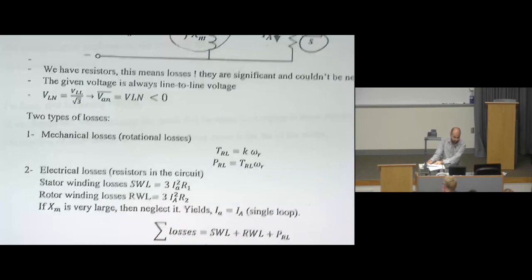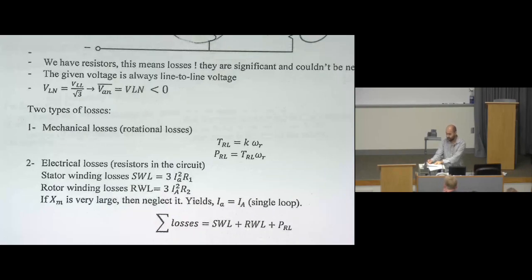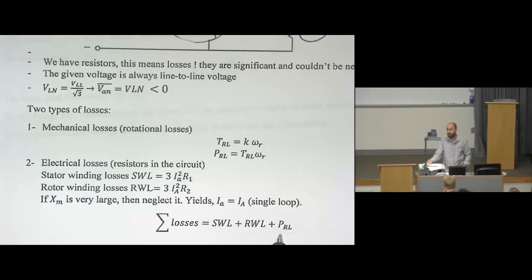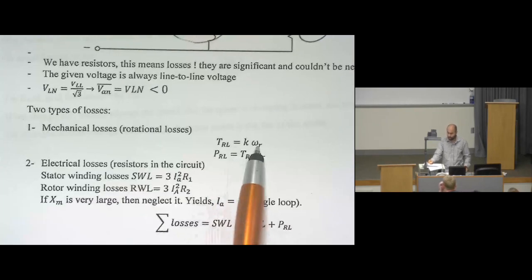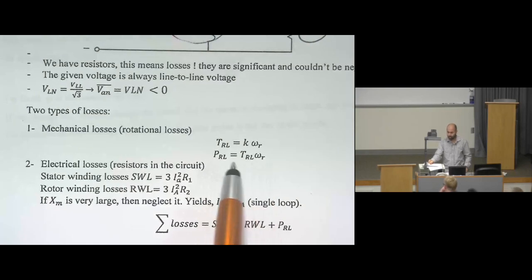The sum of losses is electrical plus mechanical, meaning stator winding losses plus rotor losses plus rotational losses. Most likely the rotational losses are given as torque, so you need to calculate the torque first, then find the power using P equal T times omega, and from there you can find the power.